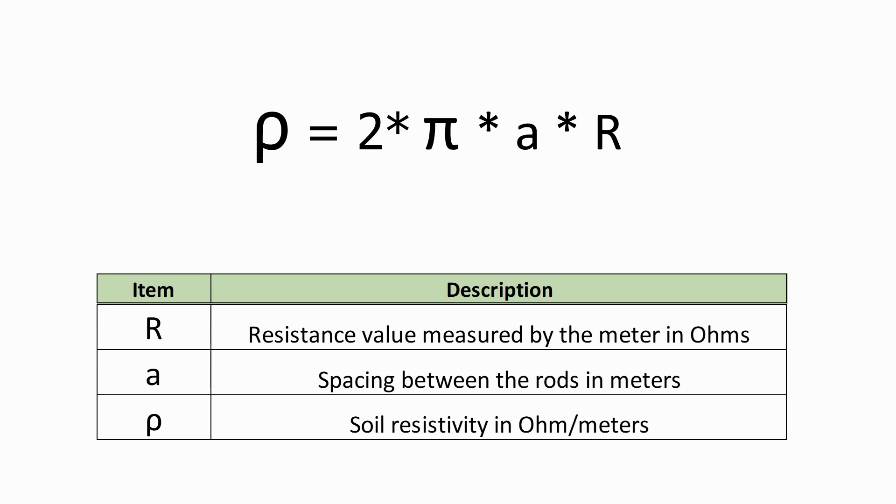Where R is the resistance value measured by the meter in ohms and A is the spacing between the rods, measured in meters. The soil resistivity is measured in ohm meters.